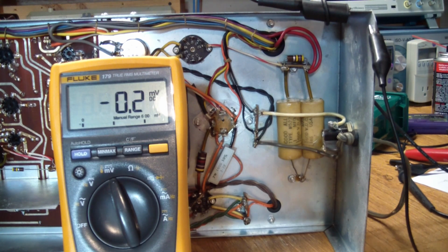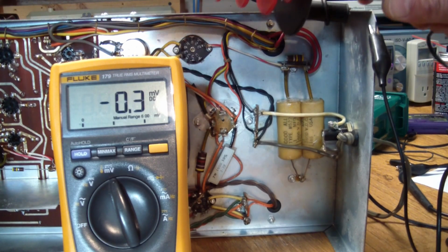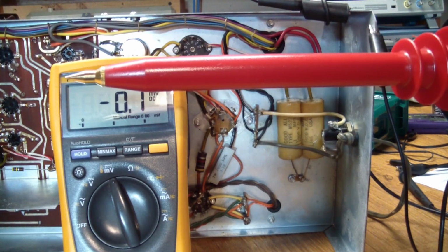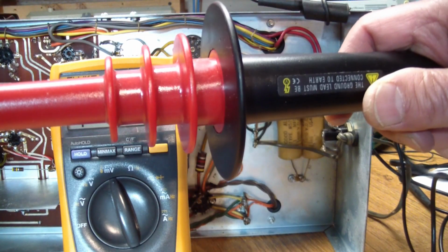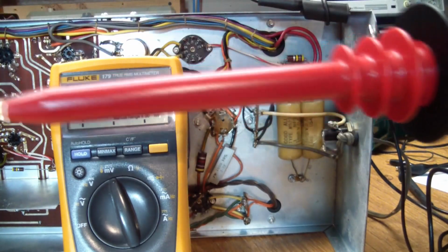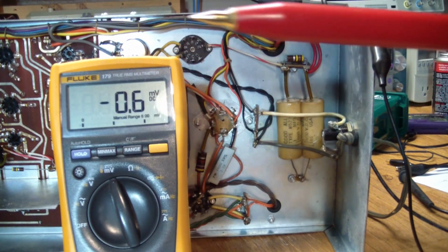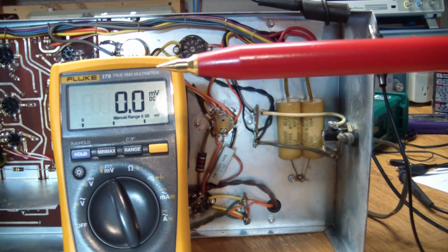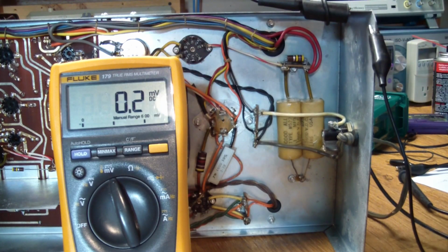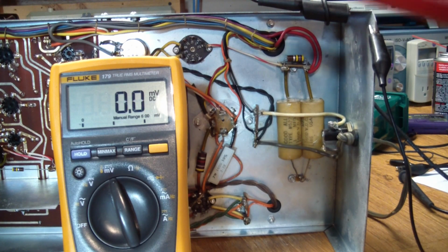Now, to measure high voltages, you need, again, to be very careful. And another thing you need to use is something called a high voltage probe, which looks like this. Kind of looks like a miniature cattle prod. It plugs into your meter, and what this does in a nutshell is it divides the voltage you're reading by a factor of 1,000. So what that means is if you're measuring 1 kilovolt, the meter is going to read 1 volt.